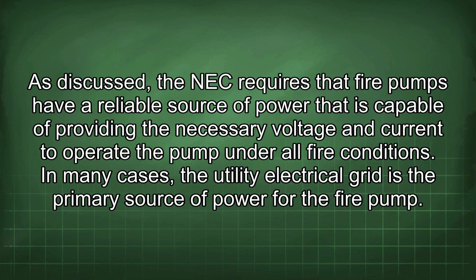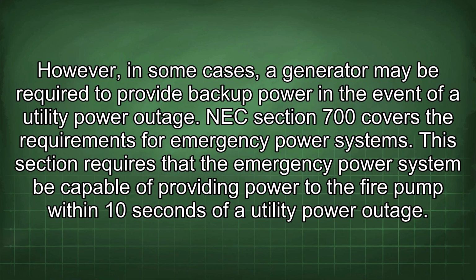The emergency power supply. As discussed, the NEC requires that fire pumps have a reliable source of power that is capable of providing the necessary voltage and current to operate the pump under all fire conditions. In many cases, the utility electrical grid is the primary source of power for the fire pump. However, in some cases, a generator may be required to provide backup power in the event of a utility power outage. NEC section 700 covers the requirements for emergency power systems. This section requires that the emergency power system be capable of providing power to the fire pump within 10 seconds of a utility power outage.